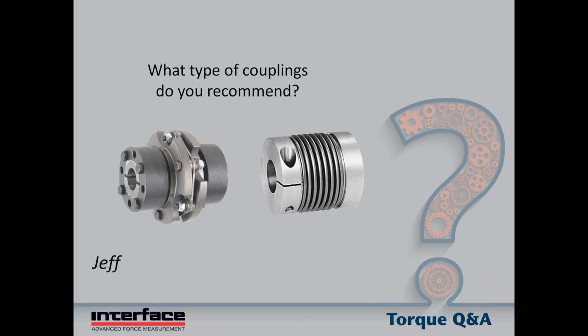Universal joints can apply a lot of extraneous loading as they rotate, so you need to take extra care to protect the torque sensor when using something like that. A gear coupling can provide a lot of thrust loading under torsion, and they don't mesh cleanly, so you have vibration and things to deal with in the measurement. So those are less desirable as well. In fact, gear couplings we quite pointedly do not recommend.